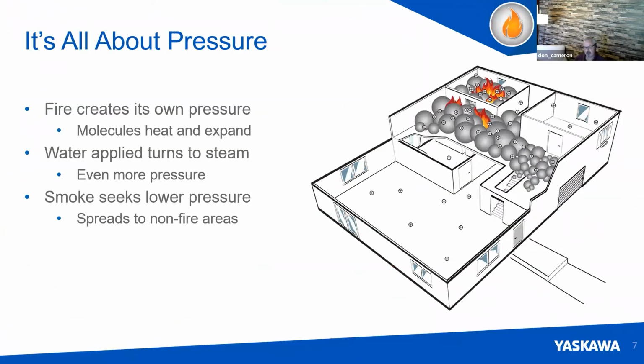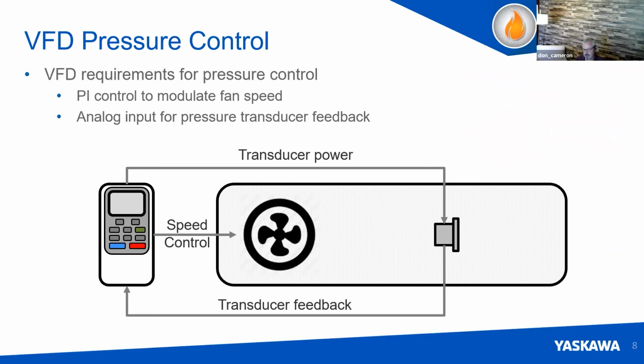And pressure, that's what we're trying to control in a fire situation. And fire creates its own pressure. And when you turn it to steam with water, it creates more pressure. And you're always seeking the lowest pressure. The smoke tries to go there. So it's a very complicated, building-specific situation. But whatever it is that you need to do with a drive to manage that, it can be programmed to do that. Typically, most common is having a transducer that is fed back from the stairwell to measure the flow and/or the pressure to modulate that speed.